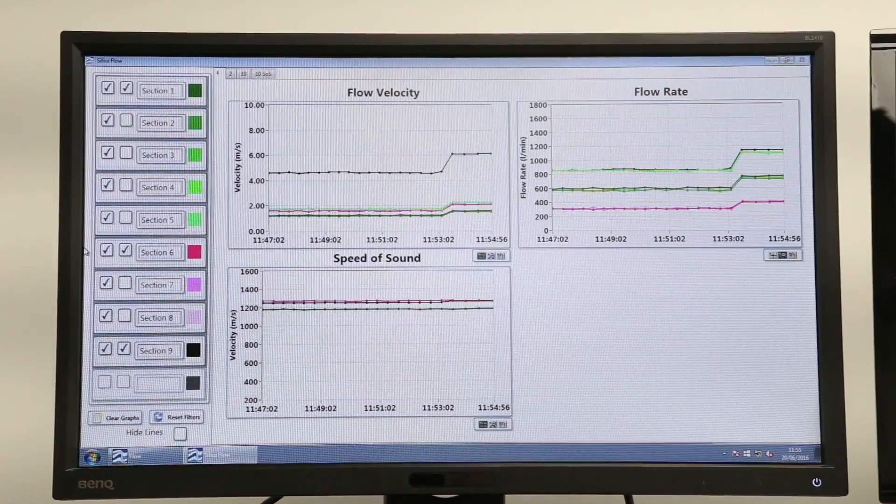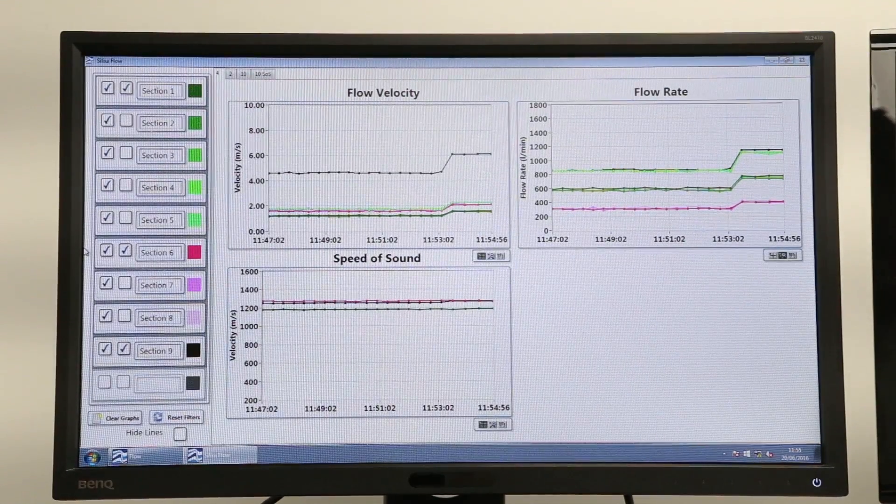As we increase the flow rate, you can see that all nine sections have an increase in flow speeds. However, our sound speeds remain constant as the flow medium hasn't changed.